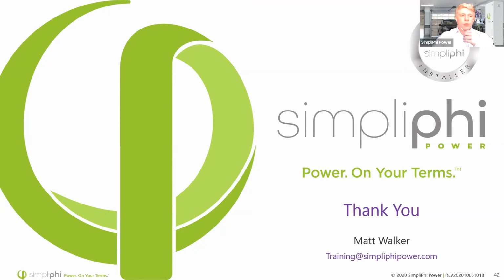What would be the next battery generation? We actually just came out with our SimpliPhi battery. This is very similar to our Phi battery, except it has a stronger BMS with communications, so it's able to really communicate with communicating inverters. Right now, the Sol-Ark is the communicating inverter, and we're working on expanding that list. By communicating with the inverter, the SimpliPhi is going to essentially tell the inverter how to treat it. It's going to say, hey, I only want to be charged at 37.5 amps, or I only want to be discharged at 37.5 amps. This builds in more safety and security in your system and keeps the battery lasting as long as possible because you know it's being treated well. Many of those settings are auto-populated when you connect the communications from the battery to the inverter, leaving you with less work to do as far as programming.